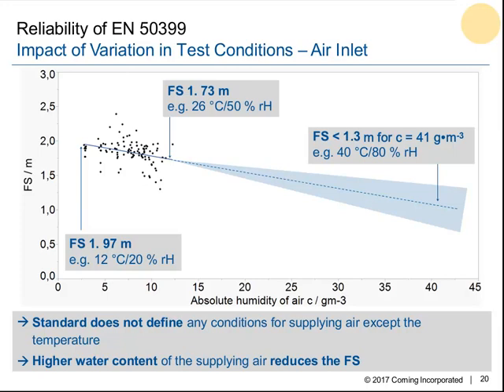In October in Orlando, where this IWCS conference was, we had something like 30 grams per cubic meter, and that was for me already an extreme. However, this 41 grams per cubic meter would still be allowed by the standard because this would account to something like 40 degrees C and 80% relative humidity. That would be within the standard. But the extrapolation shows that here we would have a flame spread which would be below 1 meter 30. So this would be a B2 rating for our C cable just because of the humidity. And again, the standard is not defining anything about the humidity.